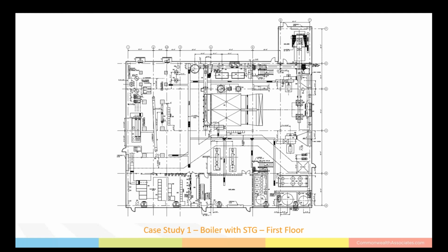To the lower right on the first floor is the water treatment area, chemical feed, and storage tanks, as well as forwarding pumps. In regards to access, on the left side of the building, there's a roll-up door for an 8-foot wide aisle that traverses through the plant and ends on the right side where there's an access hatch that extends up to the top floor for moving equipment from the ground floor to any of the floors above. Also in the floor is a trench to handle wastewater that extends into multiple areas of the plant, including under the steam turbine, maintenance shop, the water treatment area, and to the blowdown tank at the top of the page. Along that wall at the top of the page is an ash conveyor that carries ash from the boiler along that wall to the ash silo in the upper right corner.